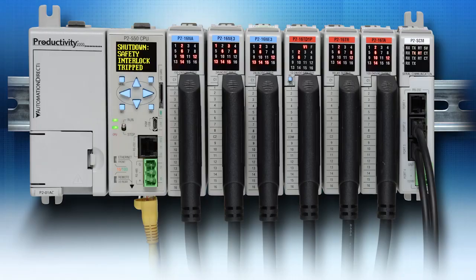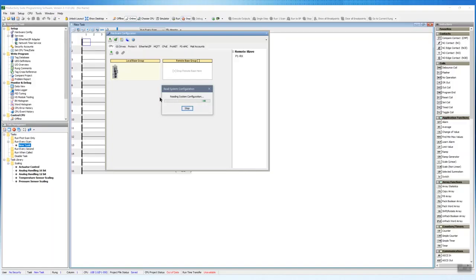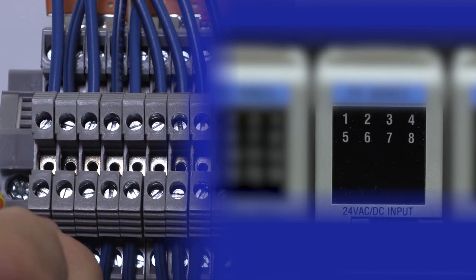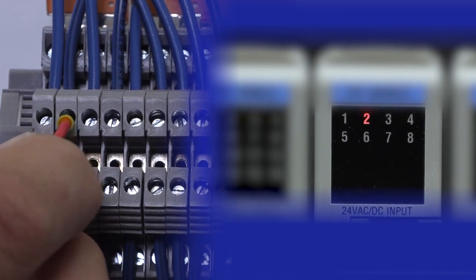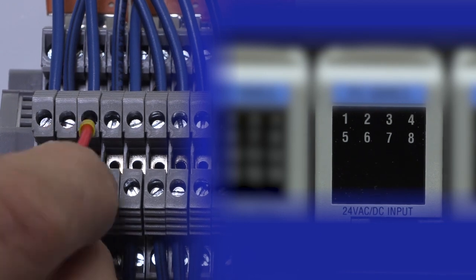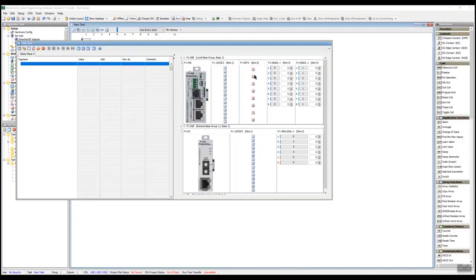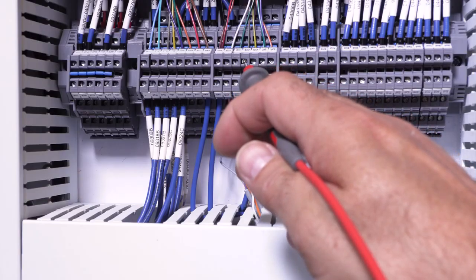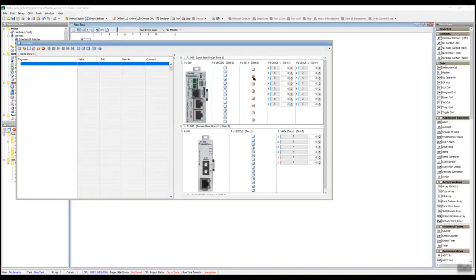Connect to the PLC and configure it with the I/O installed. Use a jumper wire to apply power or common if your inputs are sourcing to each input terminal block, making sure the correct input is activated in the PLC. Next, use the PLC's programming software to enable each discrete output one at a time and verify the selected output turns on and off as expected. Verify this at the expected terminal block. Some discrete inputs and outputs may require activation of the safety system if equipped. If this is the case, connect the appropriate safety inputs, activate the system normally, and continue with the testing.